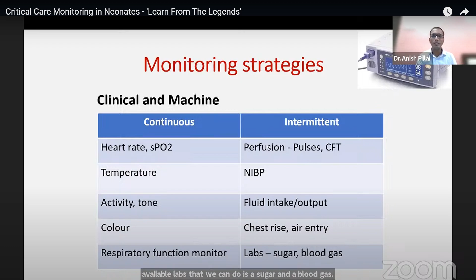If the child is inside the incubator, sometimes you have to wrap the child. So you can't even see the color or the chest if the incubator is not there. The pulse oximeter should have a neonatal probe. There should be a battery backup, and preferably a good real-time technology like SET technology. It is prone to artifacts, so that alone may not be very, very reliable. As the ambulance moves, as the baby moves, there could be probe displacements, and frequent movement artifacts can happen.